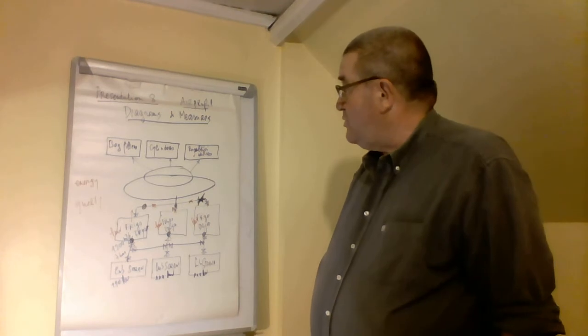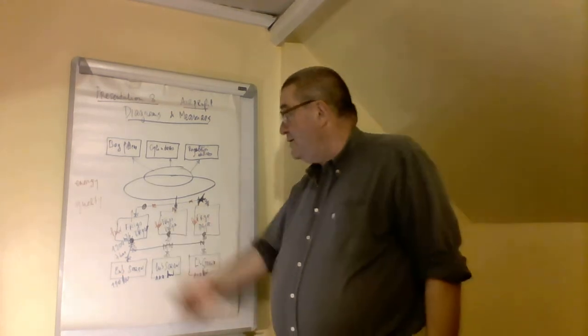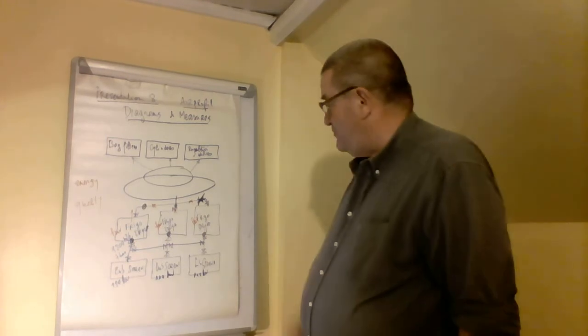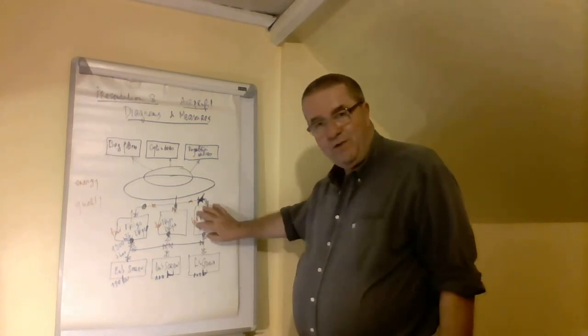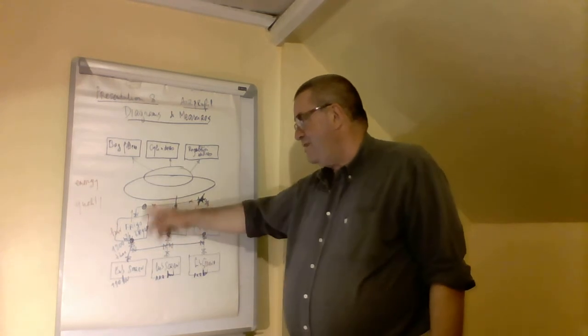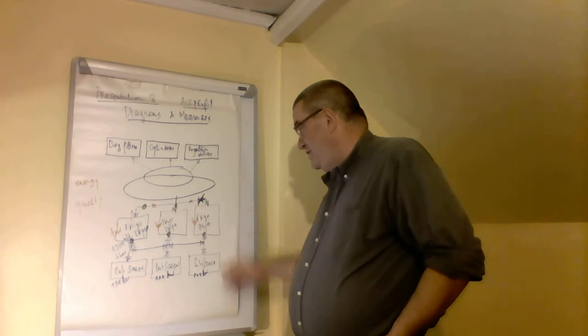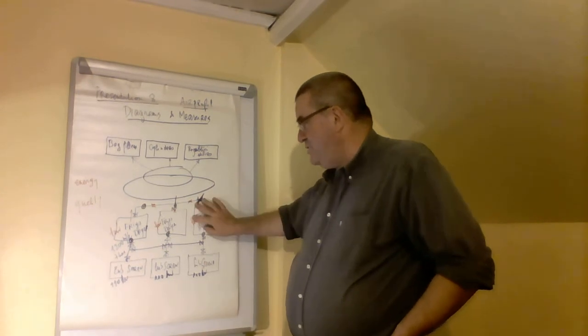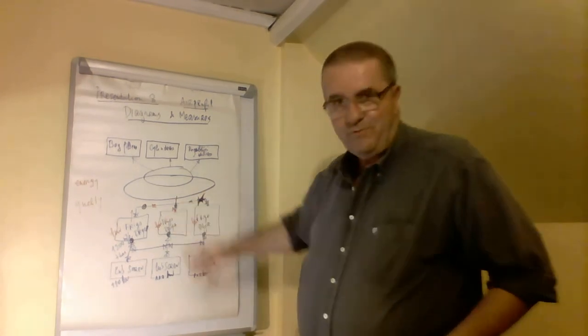Okay, so for pressure, I would say that my diagram is rather better, because if you have a block of ice in one of the dryers, the other will have a bit more air than expected, but if it is blocked completely, you do not have the pressure drop that you would have had if you have only one dryer and ice in this dryer.